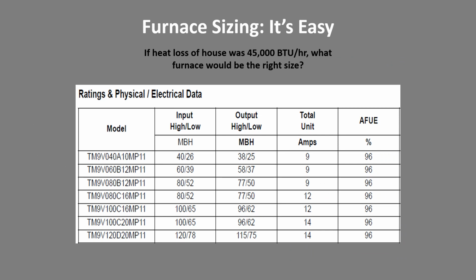Furnace sizing, it's relatively easy. All we're trying to do is to find the right size of the furnace for the heat loss of the house. Say we had a heat loss of the house at 45,000 BTUs. What furnace would be the right size? Well, this one, even on high speed, on our high fire, would be around 40K. That's too low. We're not going to do that. This one would give us 60K on high and roughly 40K on low. Sounds to me like a really good fit.